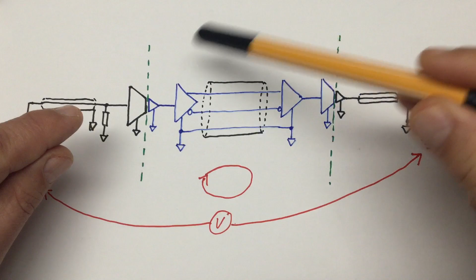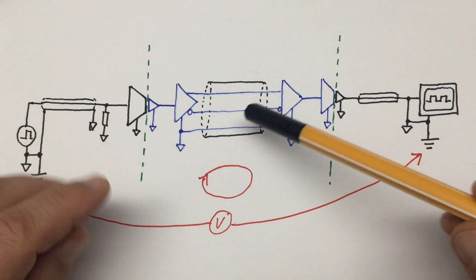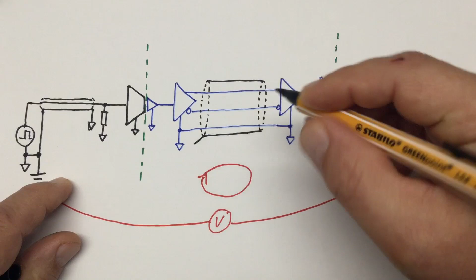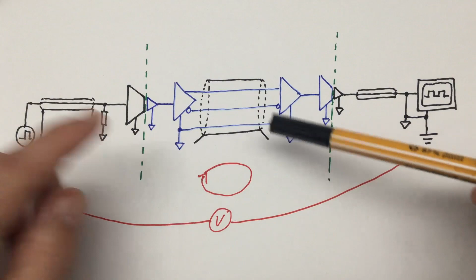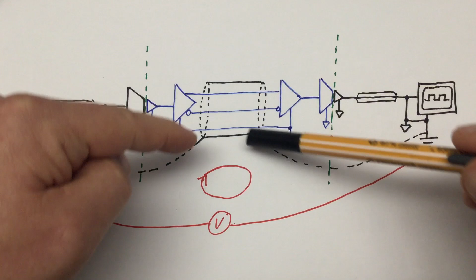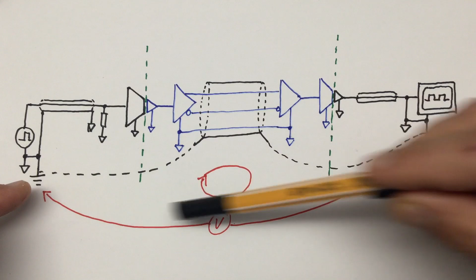Anyway, using a shielded twisted pair is obviously better than using an unshielded one. That's statement number 1. And then it gets complicated, because we have to connect that shield somewhere. Rule number 2: a shield should never be connected on both sides, only on one side, because if we connected the shields on both sides, for example to mains earth, we would create another ground loop.